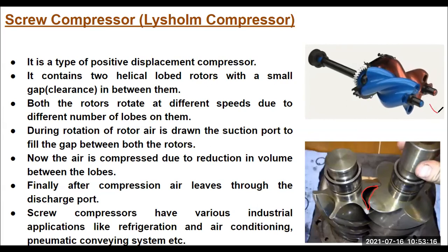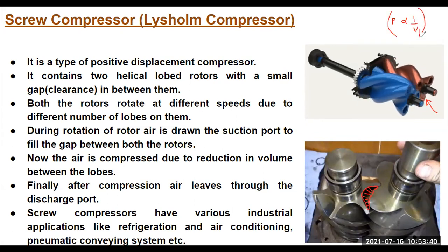So at the inlet, when air enters from this side, the air will be trapped in the gap between these two rotors. Since the volume of the air will gradually reduce, and we already know pressure is inversely proportional to volume from the ideal gas equation, if volume reduces, then simultaneously its pressure value will increase. So this is the exact mechanism behind the screw compression.